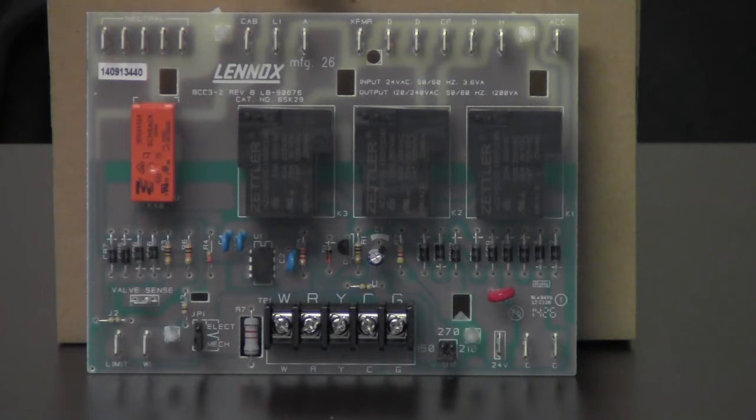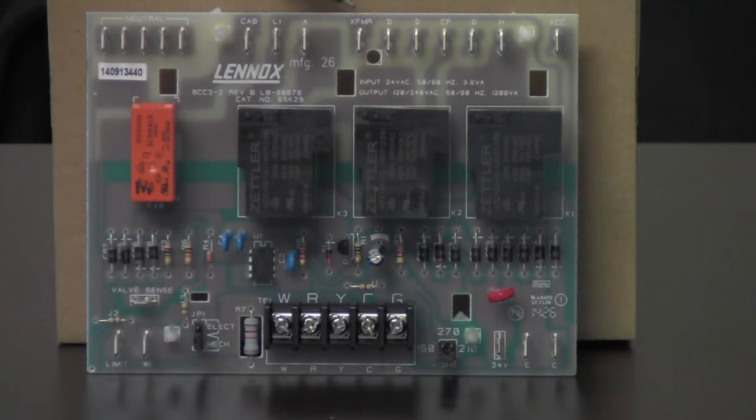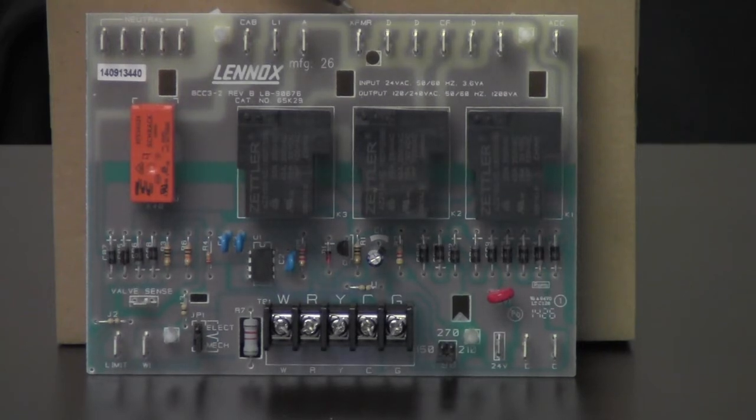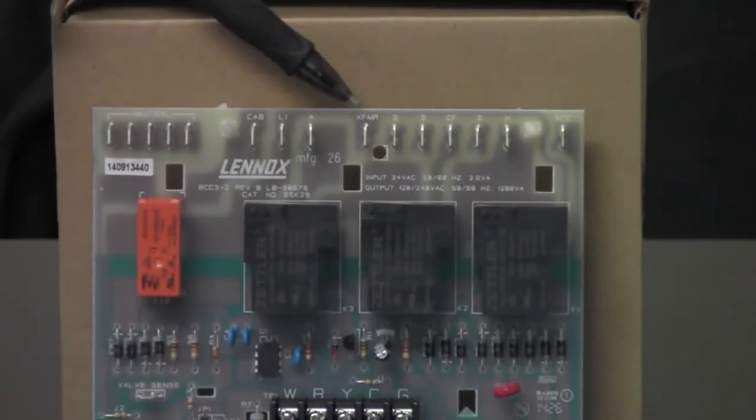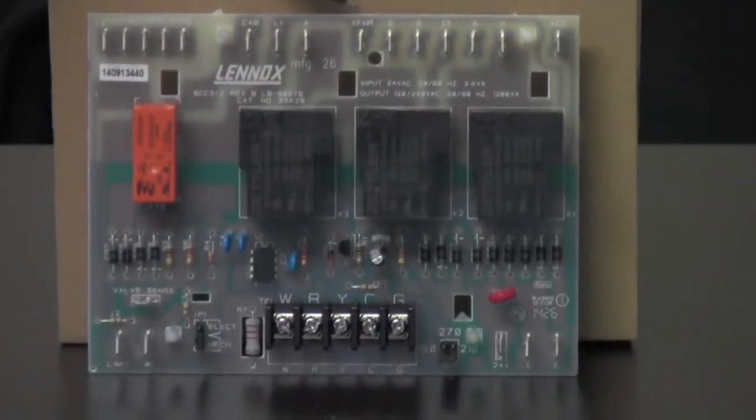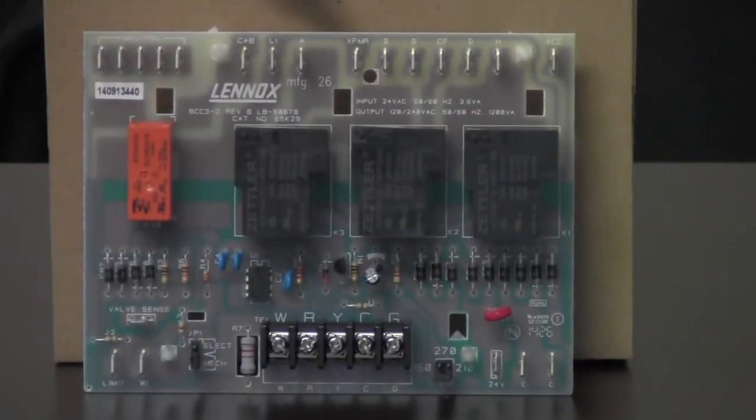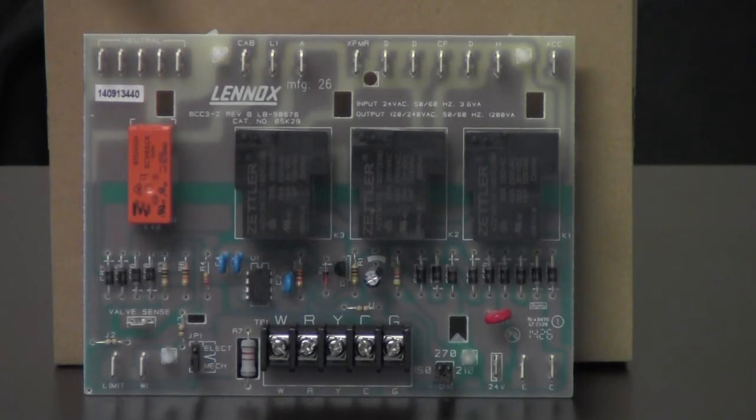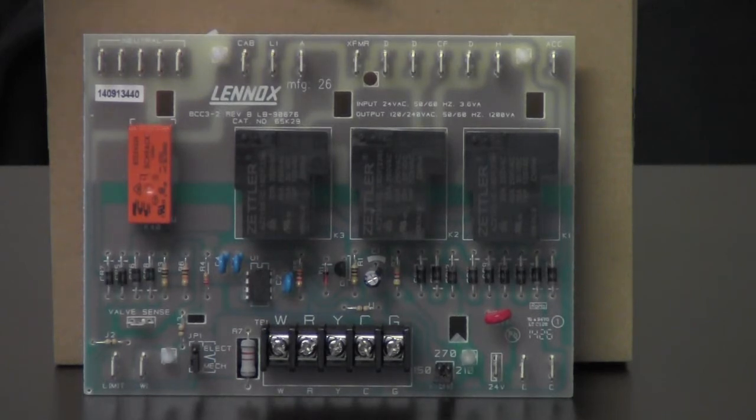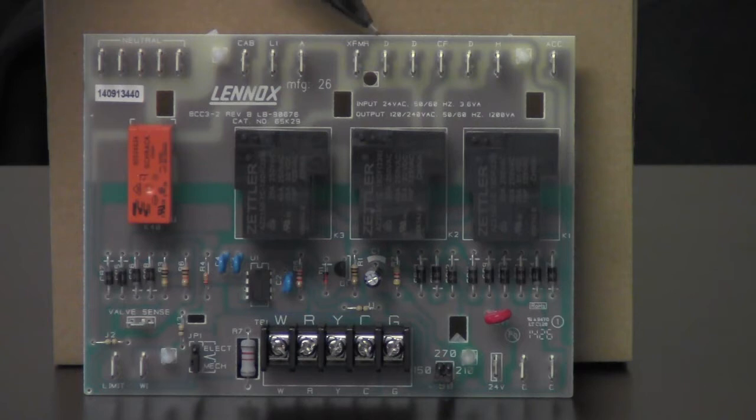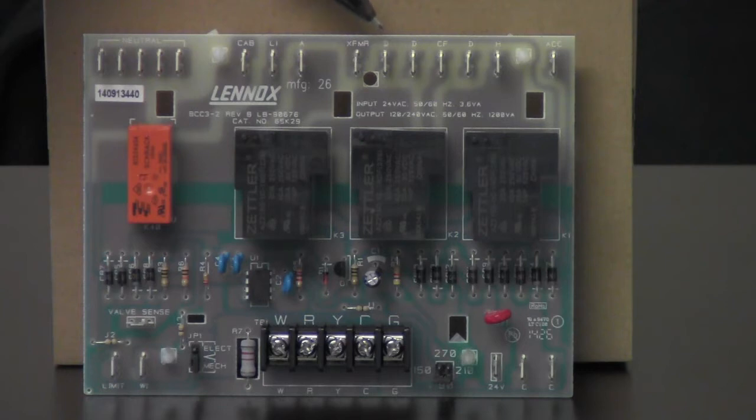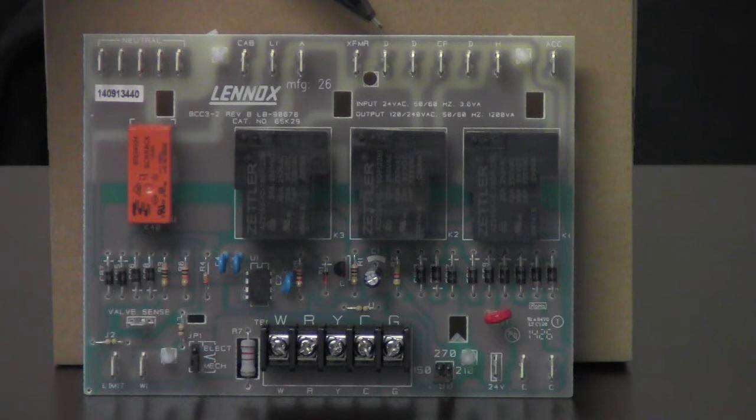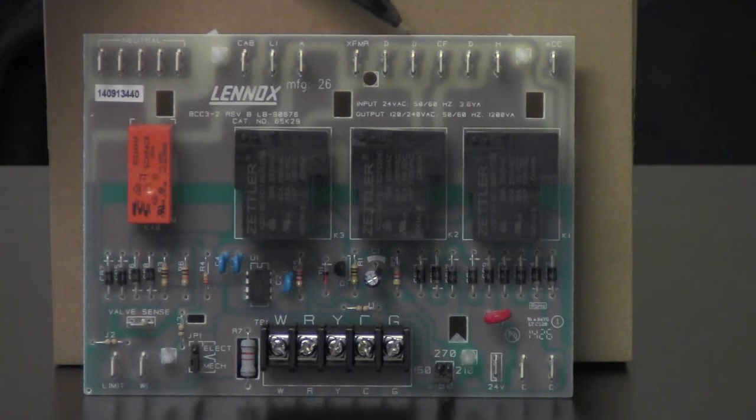Next one over is XFMR, that's for our transformer, the primary side. So our black lead from our transformer will go to XFMR, and your neutral from the transformer will hook to your neutral. Next to that we have some dummy terminals or D. That stands for dummy terminals. What those are used for is unused blower leads. So if you've got several speeds on your blower motor, like a five speed blower motor, and you need a spot to put those leads that you're not using, you can put them to the D terminals.